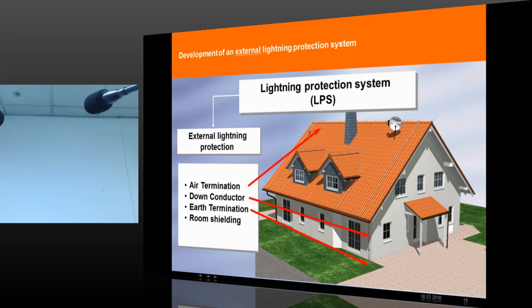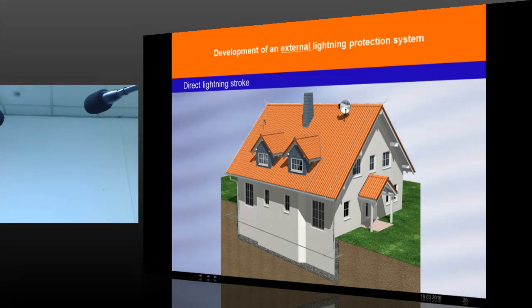Part of external lightning protection: air termination, down conductor and earthing, and a little bit of room shielding. And what is happening? In case of a lightning strike, the current flows and a high potential is created. In several countries, people believe that current goes to earth, and they try to put deeper and deeper earth electrodes because the current goes very much inside the ground. This is the belief, but it is wrong. Lightning current flow is a surface phenomenon. Current always tries to flow through the surface.